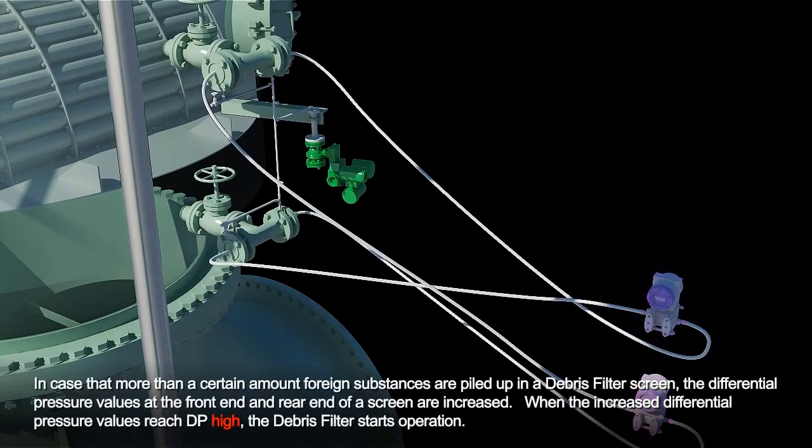In case that more than a certain amount of foreign substances are piled up in a debris filter screen, the differential pressure values at the front end and rear end of a screen are increased. When the increased differential pressure values reach DP-high, debris filter starts operation.